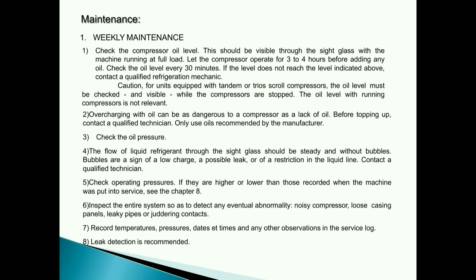2. Overcharging with oil can be as dangerous to a compressor as a lack of oil. Before topping up, contact a qualified technician. Only use oils recommended by the manufacturer. 3. Check the oil pressure. 4. The flow of liquid refrigerant through the sight glass should be steady and without bubbles. Bubbles are a sign of a low charge, a possible leak, or of a restriction in the liquid line. Contact a qualified technician.